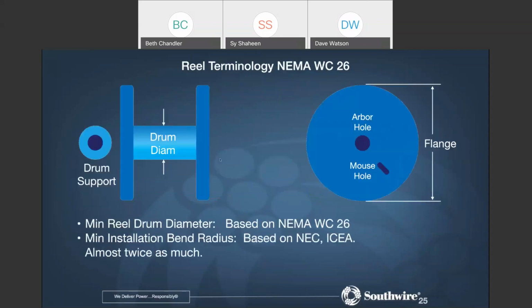All right, so real quick here, a little terminology that you may want to know about a reel. The inside is called the drum. This is called the flange. This middle hole is called the arbor hole. This is the terminology from NEMA WC26. The minimum drum is based on NEMA, so we size this drum based on NEMA WC26. The minimum installation bend radius is based on NEC, ICEA. It's almost twice as much.